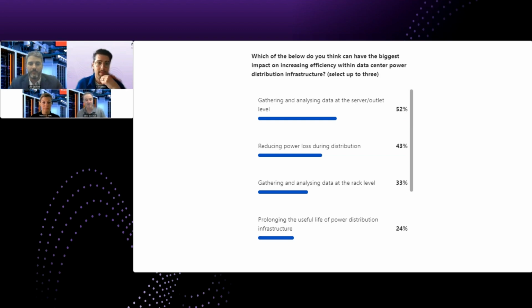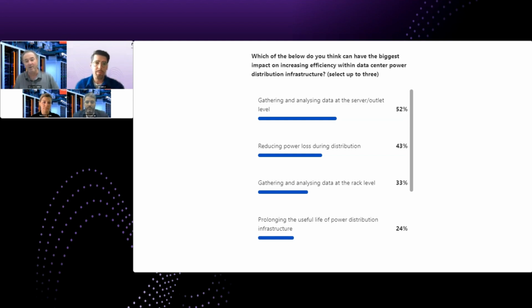What's interesting to me is the comment on distributing power at 400 and 415 volts, which is really what the rest of the world typically does. But in North America, we bring in 480 volts and convert it all the way down to 120. There are a lot of losses in those conversions, whereas if you distribute in the cabinet at 400 volts, you can use an auto transformer and avoid the efficiency losses in power conversion. Also, if you look at the chart, servers typically run more efficiently at higher voltages. So we've started to see a fundamental shift toward 400 volt solutions instead of 208 volt solutions, both being three phase.